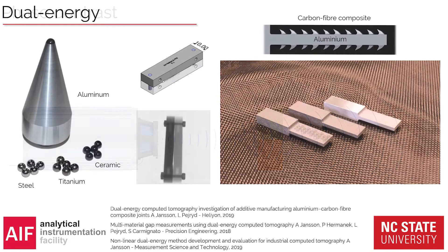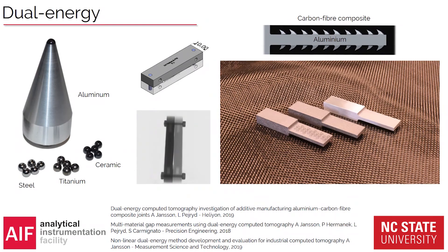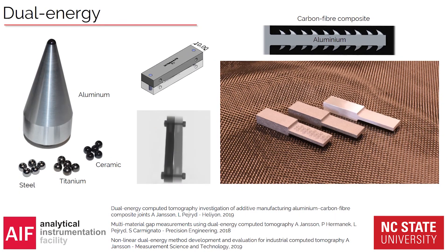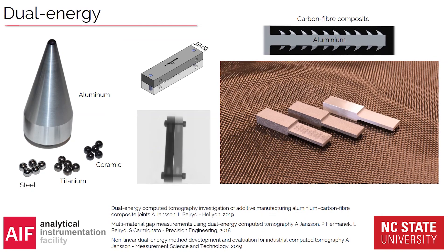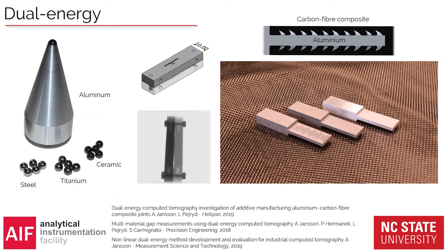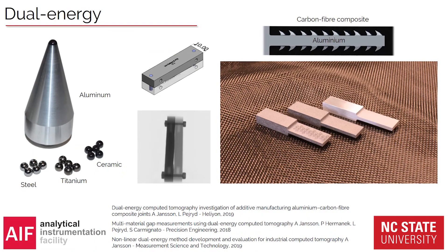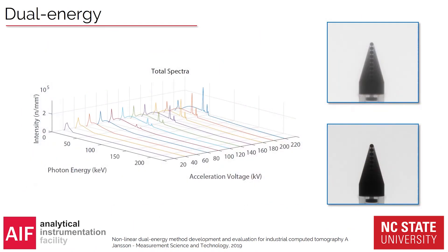You can also use dual energy. If you want to scan something with both very high-density and low-density material in the same part, you can do two different scans — one at high energy and one at low energy — and combine them to get a very nice result.